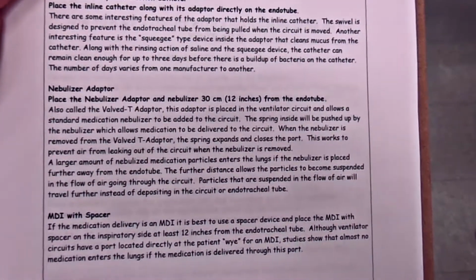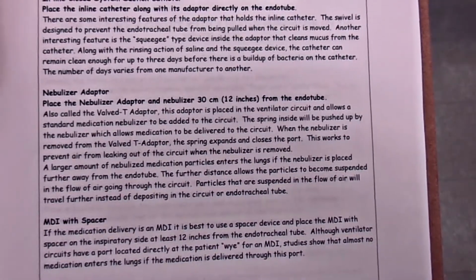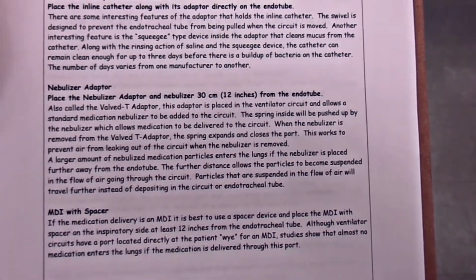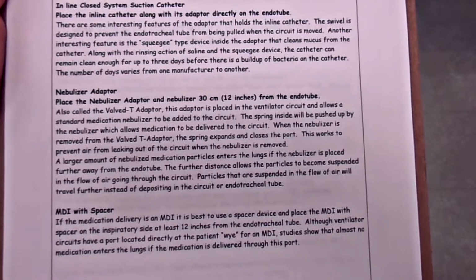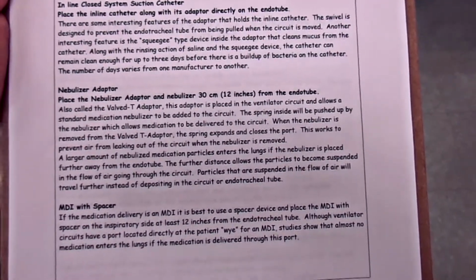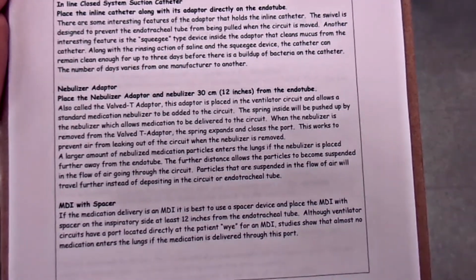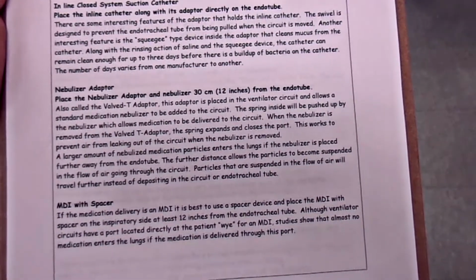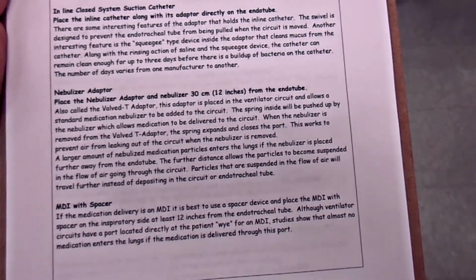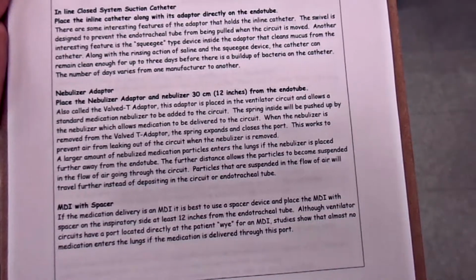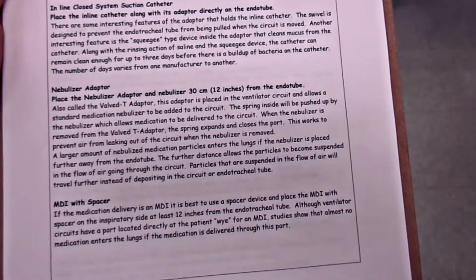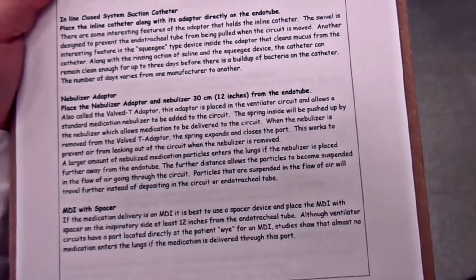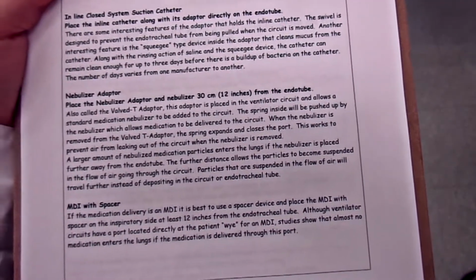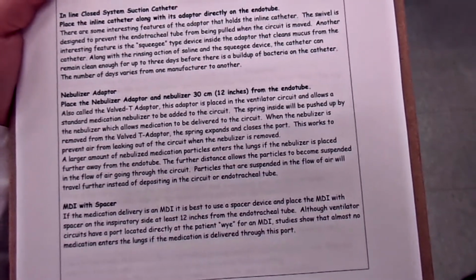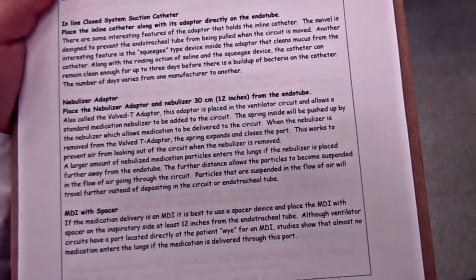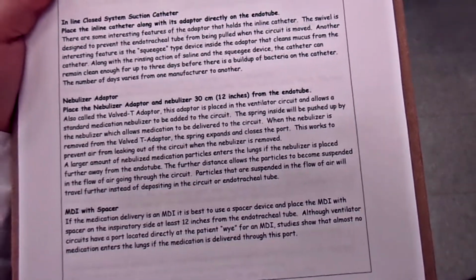There's the nebulizer adapter and nebulizer 30 centimeter, 12 inches from the endo tube. Also called the valve T adapter. This adapter is placed on the ventilator circuit and allows a standard medication nebulizer to be added to the circuit. The spring inside will be pushed up by the nebulizer, which allows medication to be delivered to the circuit. When the nebulizer is removed from the valve T adapter, the spring expands and closes the port. This works to prevent air from leaking out of the circuit when the nebulizer is removed.